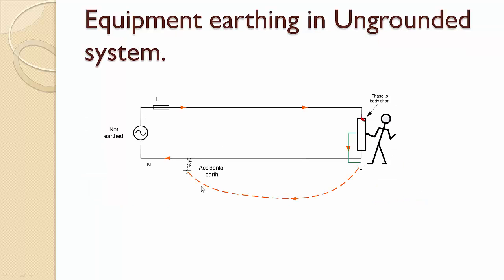One thing that might come to your mind is: even in this case, won't grounding the equipment protect against the accidental grounding? The answer is it actually does, and for this reason the equipment is grounded even in ungrounded systems. But as you can imagine, in this case there may not be a good ground at the fault point, and so the fault current may not be very large due to high impedance or resistance in the earth current path.